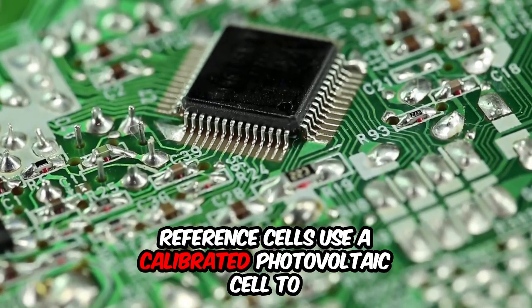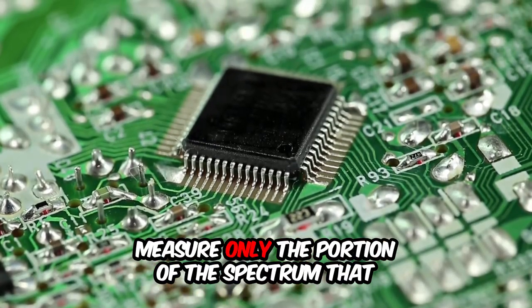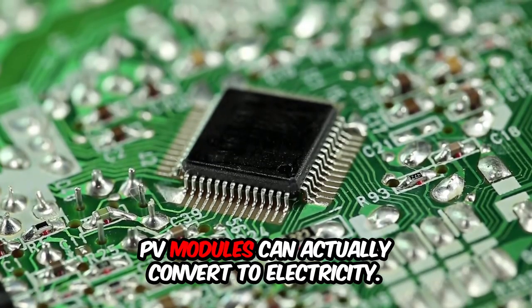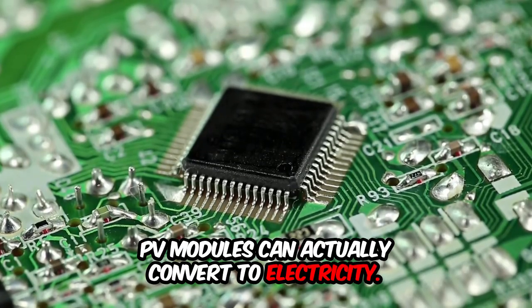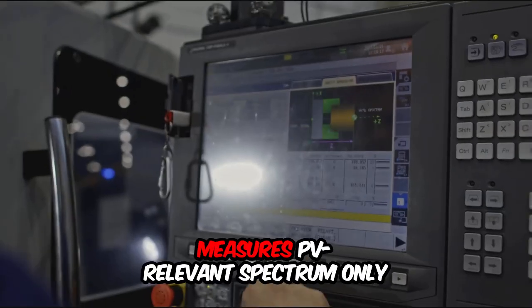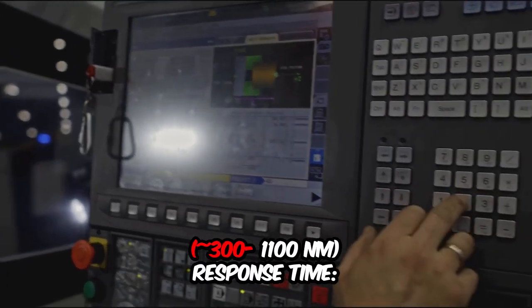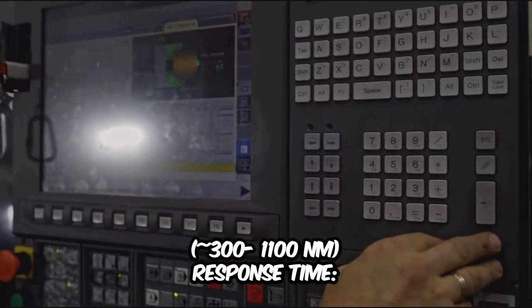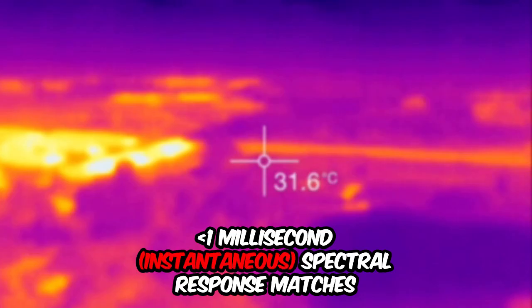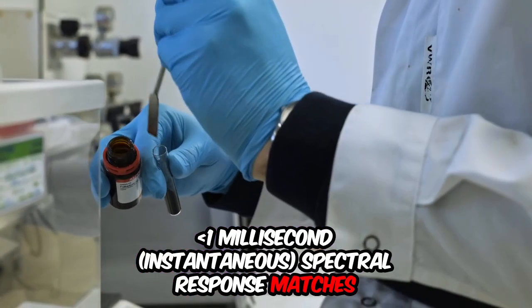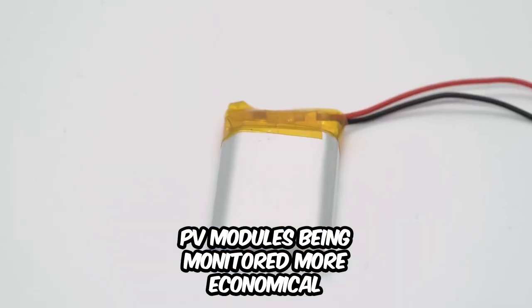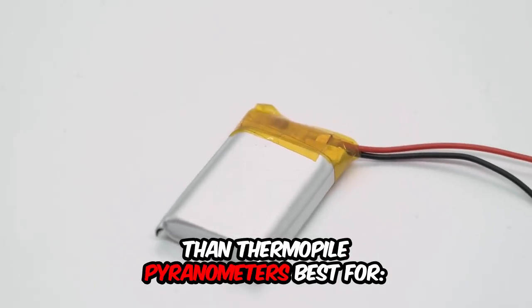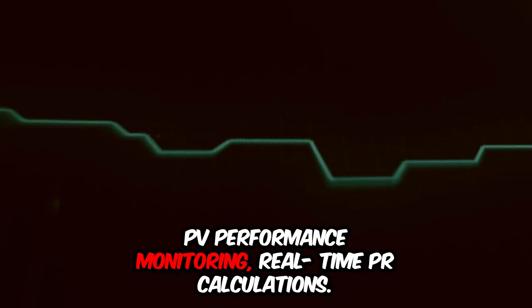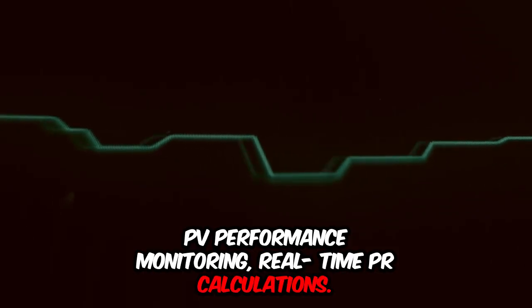Reference cells use a calibrated photovoltaic cell to measure only the portion of the spectrum that PV modules can actually convert to electricity. Key characteristics: measures PV-relevant spectrum only, 300 to 1100 nanometer. Response time, 1 millisecond, instantaneous. Spectral response matches the PV modules being monitored, more economical than thermopile pyranometers, best for PV performance monitoring and real-time PR calculations.